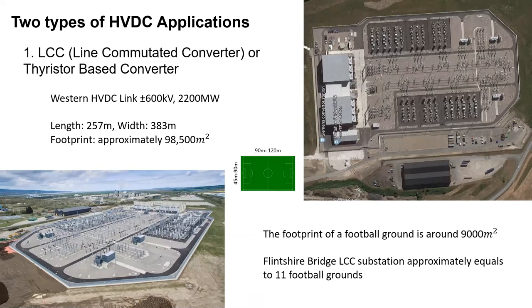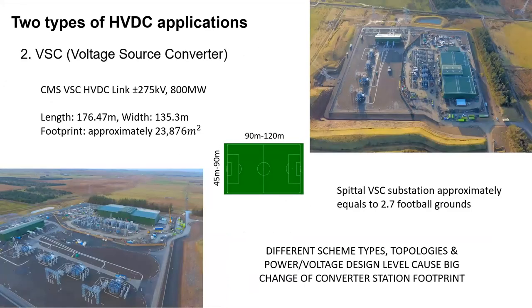This slide shows a picture of one of the converter stations for the Western HVDC link. And you could see the space an LCC based converter could need is as big as the space required to accommodate 11 football grounds, and considerably more in case the DC voltage is raised further. So if this 600 kV is raised further, this layout can really get bigger. The next application is VSC, which stands for voltage source converter. It uses IGBTs and requires less space than LCC, as can be seen from the slide.